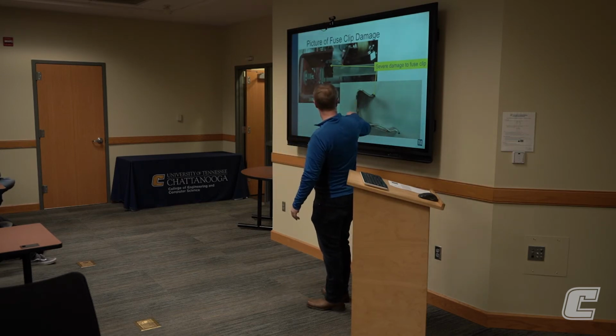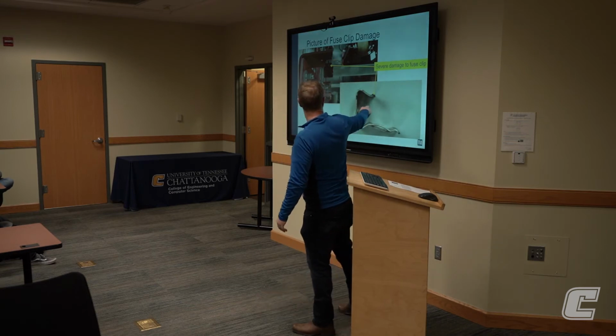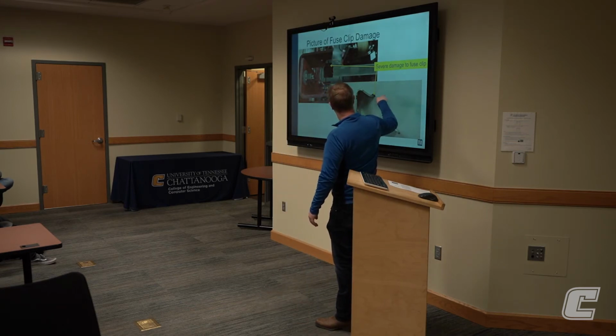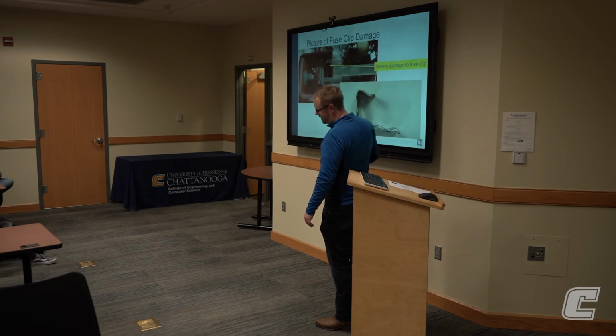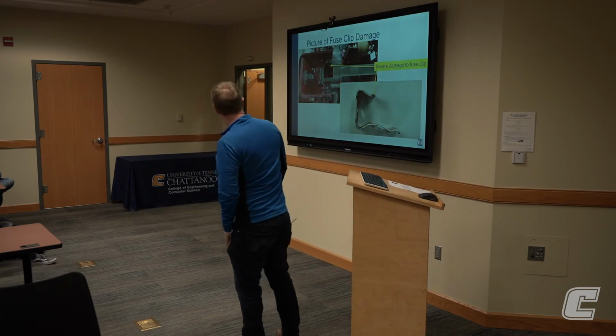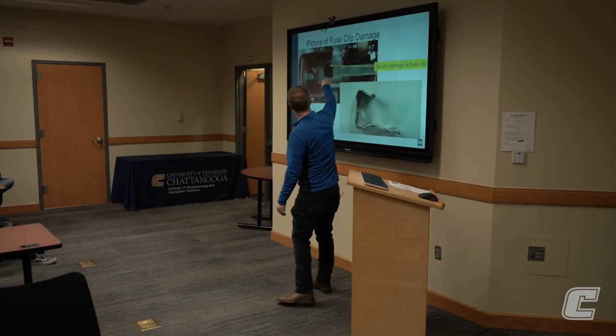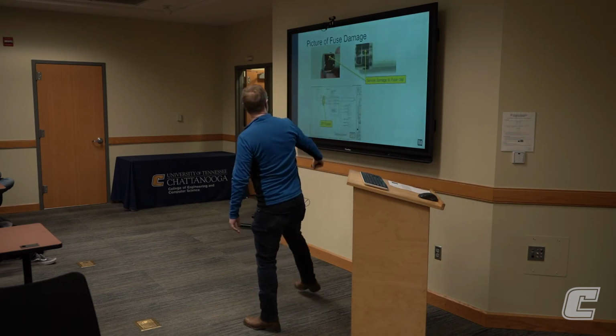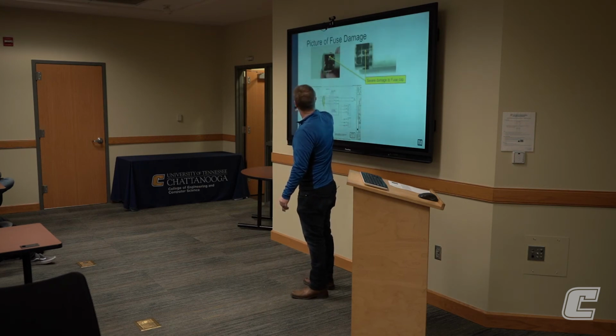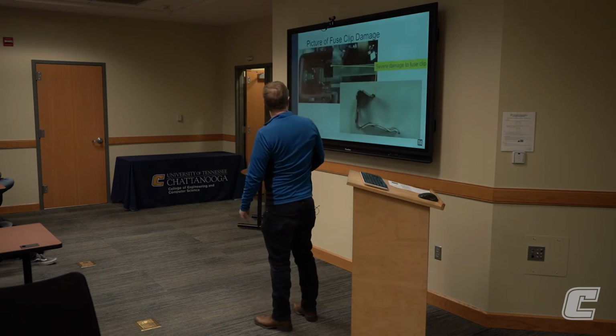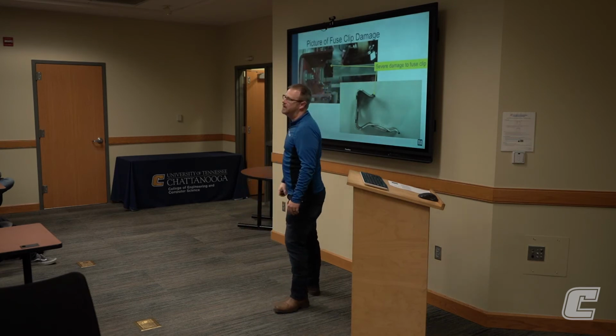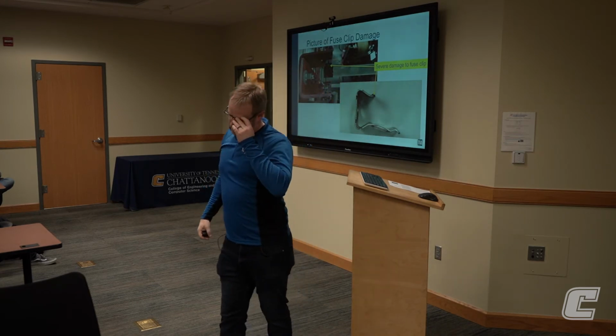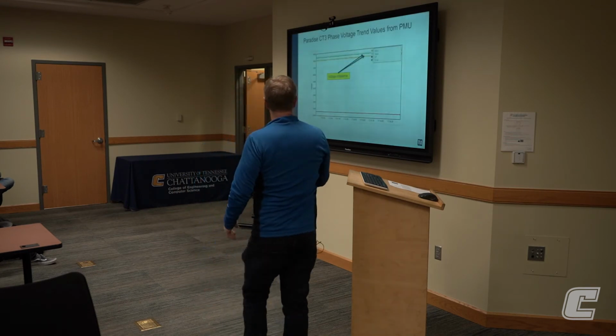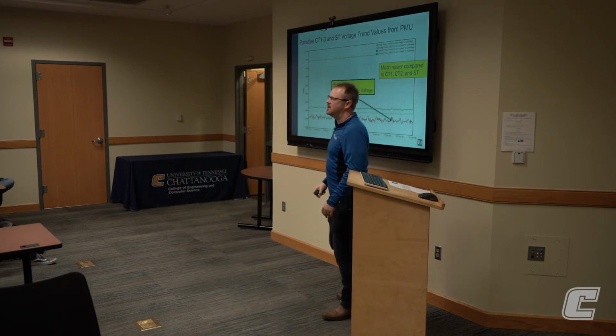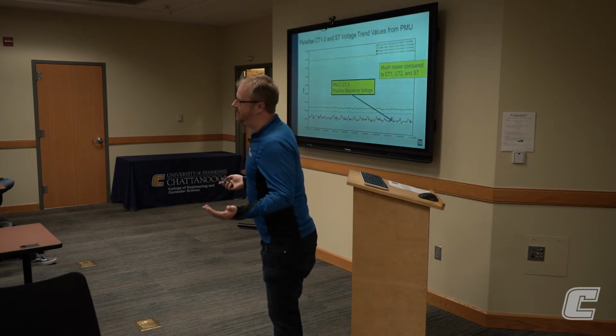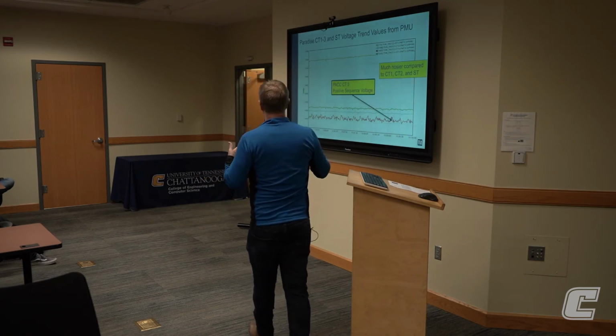And this is the fuse holder here. And you can see it's missing part of the holder. The connection is gone, has arced away. And you can see on the end of the fuse here, this is the fuse cap. I think this picture shows it. There's been some damage to the fuse cap. And what had happened was this was not seated properly and it was arcing. And that's why we were getting this very noisy voltage signal here. So the unit wasn't oscillating like we thought it could be, but there was something wrong there.